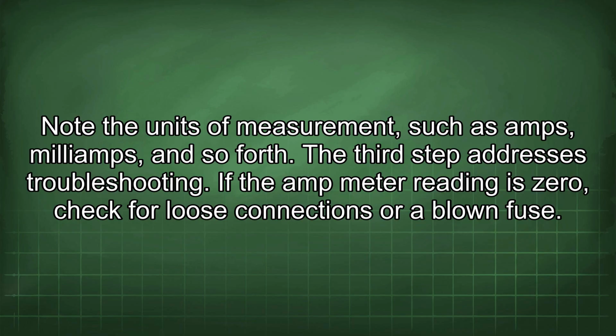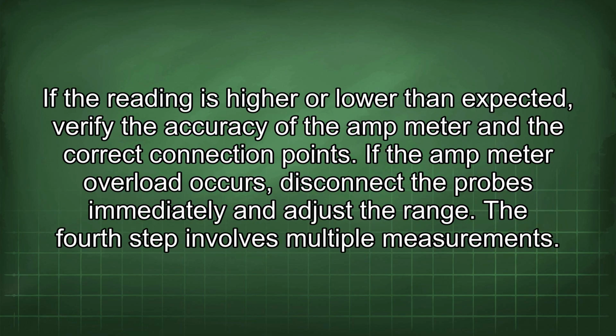The third step addresses troubleshooting. If the amp meter reading is 0, check for loose connections or a blown fuse. If the reading is higher or lower than expected, verify the accuracy of the amp meter and the correct connection points. If the amp meter overload occurs, disconnect the probes immediately and adjust the range.